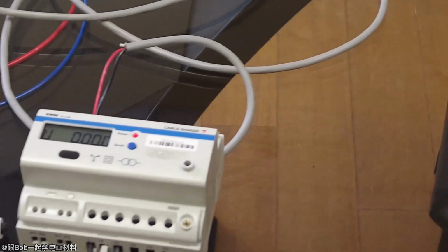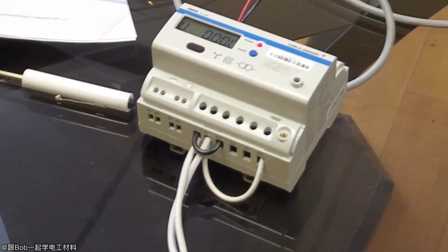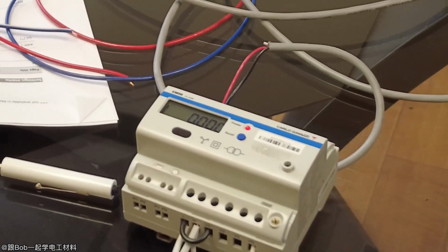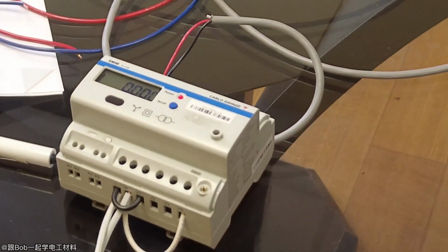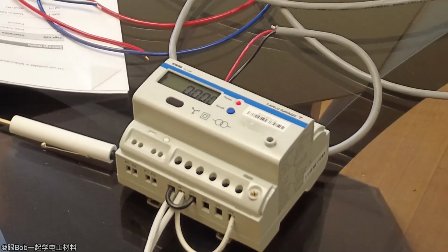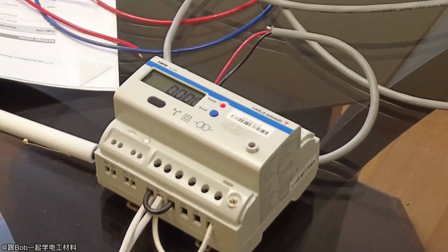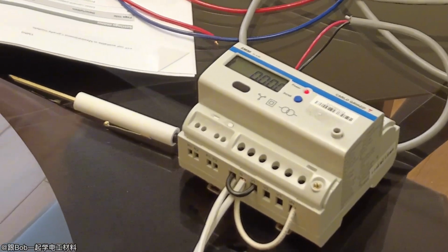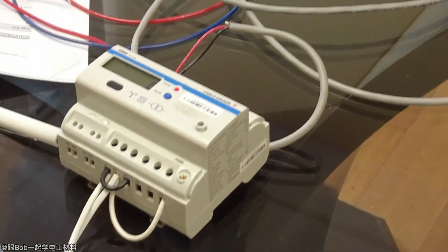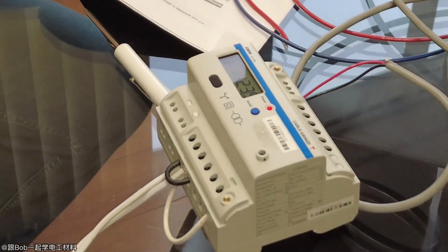Last time you showed me one piece of equipment you can hook up with RJ45, right? Yeah, the other one we have is, again, this is not the only meter we have. We have probably the broadest range of meters on the market. So if you want something with Modbus TCP, you could use one of these meters, and again, you could configure it with this software. Does this one have an RJ45 interface? No, this one doesn't use Ethernet. This is strictly Modbus. Modbus and BACnet, but only the RS485. If you want BACnet or Modbus TCP, which is Ethernet, then it would be a different meter.